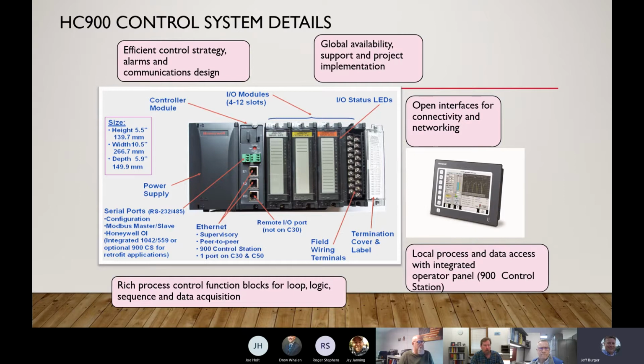It also has pre-built displays for a lot of diagnostics that you really don't get with other manufacturers. The display will go all the way down to the points on the I/O cards and tell you not only if there's a diagnostic issue, it will also tell you the firmware revision and the part number of the display, so that if you do need to replace it, you can have that part number handy to give to your local distributor.